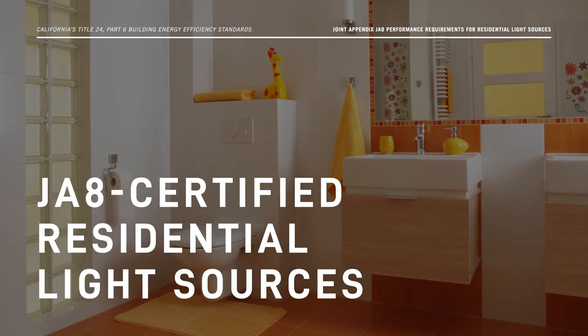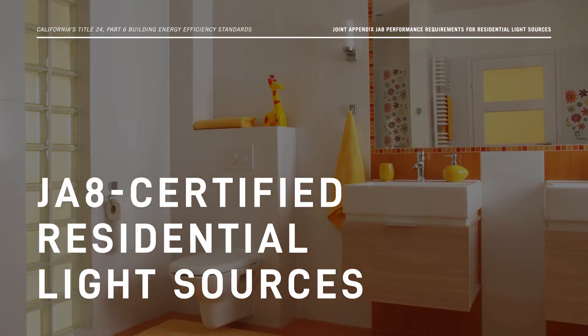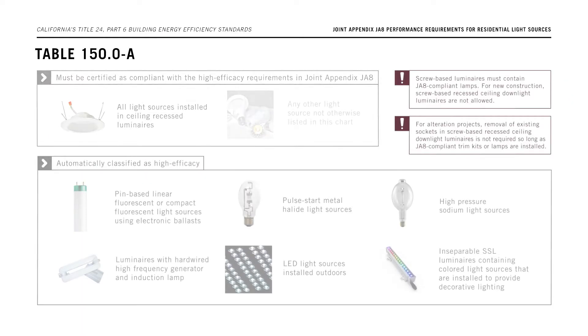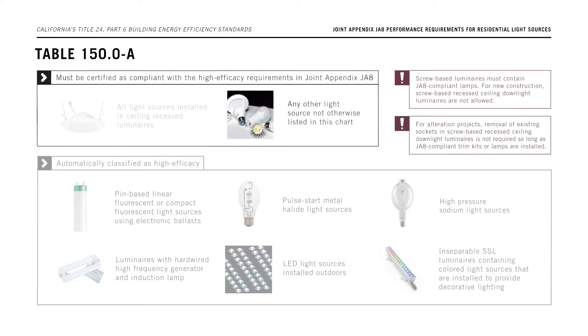Let's discuss the residential light sources that must be JA8 certified in order to be classified as High Efficacy and compliant with the Energy Code. These include light sources installed in ceiling-recessed downlight luminaires — remember, no screw-based lamps are allowed in recessed downlights — and any other light source which is not automatically classified as High Efficacy, such as indoor LED luminaires, screw-based LED lamps, and pin-based LED lamps.